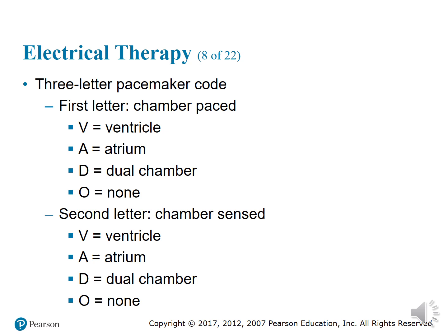The second letter in a permanent pacemaker signifies the heart chambers in which the pacemaker senses its intrinsic activity. Of course, V stands for ventricle, A for atrium, D for dual, both ventricle and atrial. O means no sensing. When a pacemaker doesn't sense intrinsic activity, it paces even if intrinsic activity exists. This is referred to as asynchronous pacing.